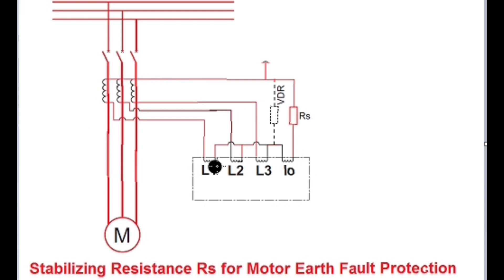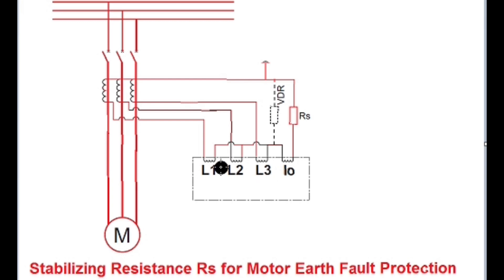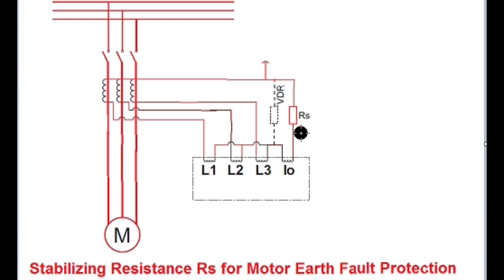Here the connection has been shown: from each phase CT secondary, one terminal is taken to the red, yellow, and blue phase coil of the relay, and the other terminal is shorted to form the neutral and taken through the residual coil or earth fault coil of the relay, then back to the CT via a resistance called the stabilizing resistance.